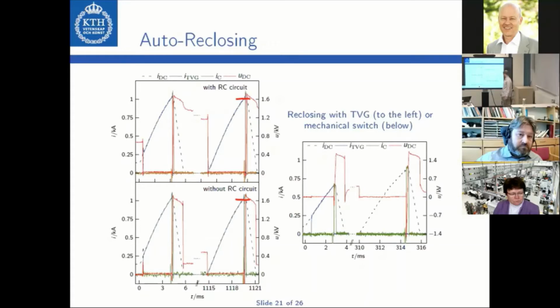The thing is, though, as you saw, that reclosing could be attempted after 1 second. This is quite long for practical applications, but the triggering unit that was sold with the triggered vacuum gap could only be operated once per second. So this was a limitation. Therefore, we have investigated an alternative reclosing strategy based on the mechanical switch, which you can see here on the right-hand graph. The reclosing here already takes place after 300 milliseconds. The dashed line now corresponds to the current in the mechanical switch. As you can see, the triggered vacuum gap is actually never operated in this case, and the mechanical switch conducts the current all the time.